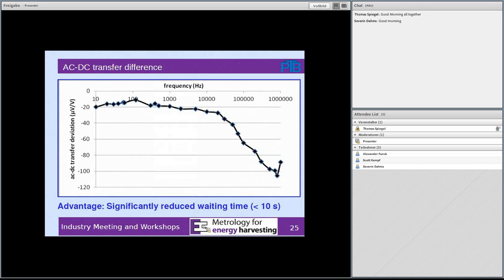Here we have the AC-DC transfer difference, which again goes down to about 80 parts per million at 100 kilohertz. We also measured up to 1 megahertz, where we get about 100 microvolts per volt. So this could also be used as a standard AC-DC transfer device.